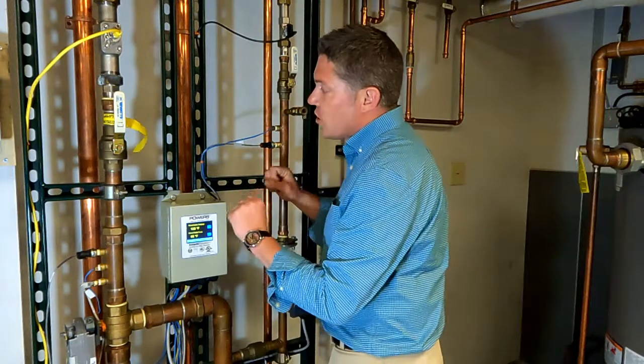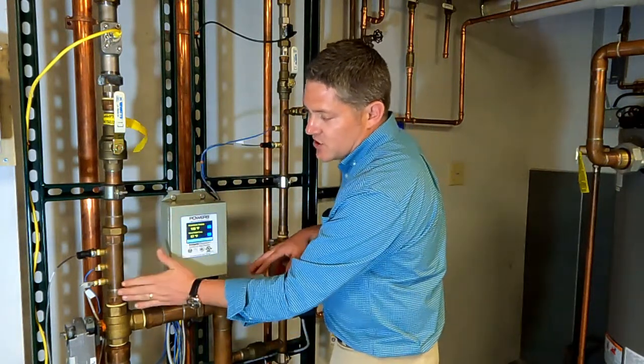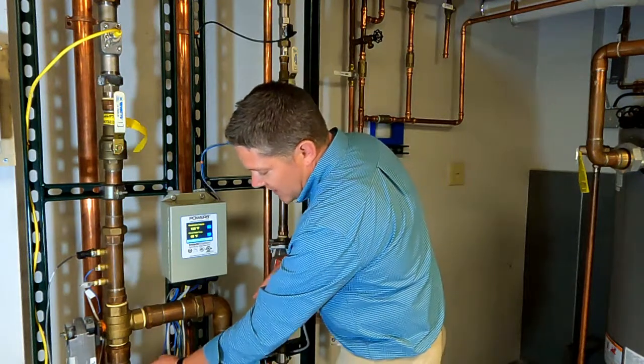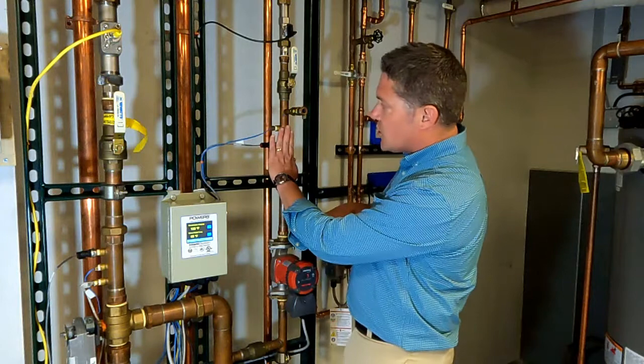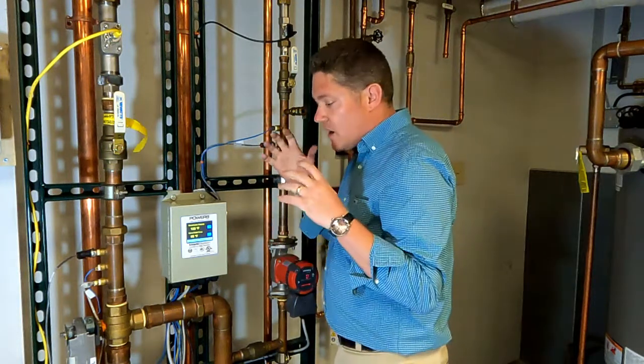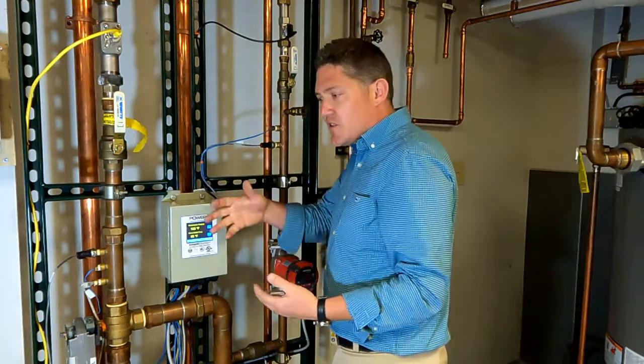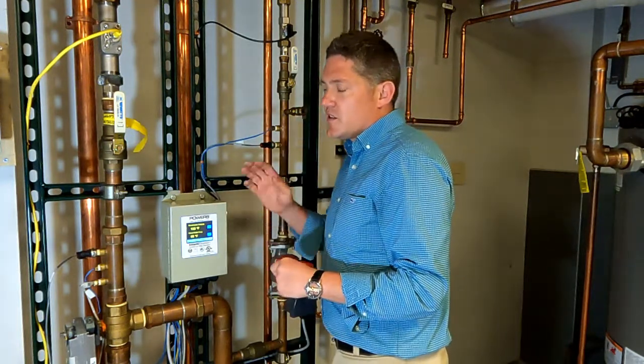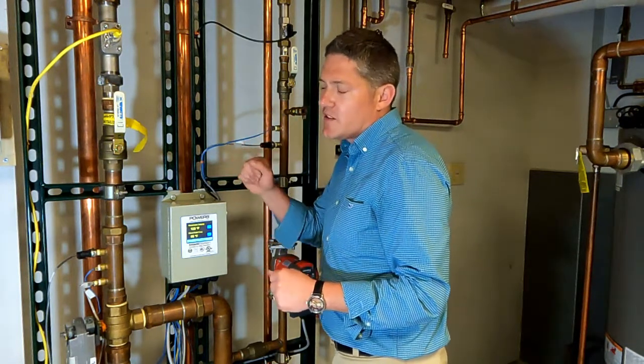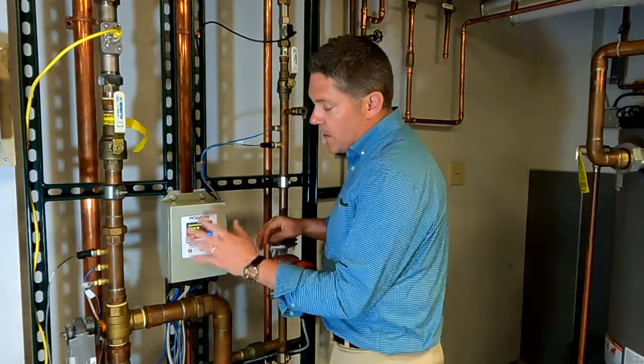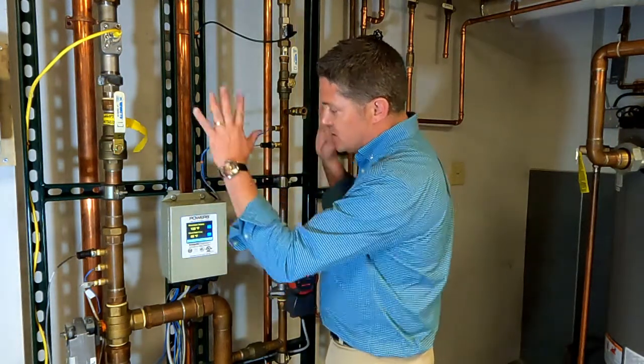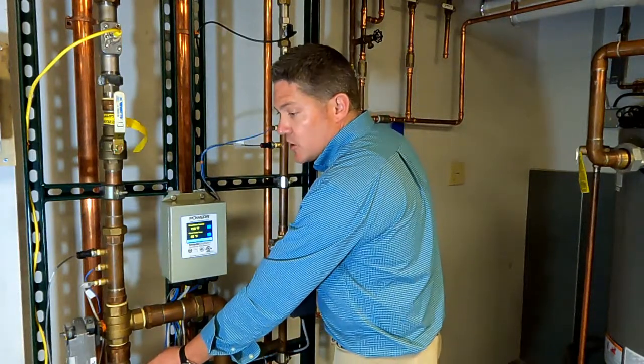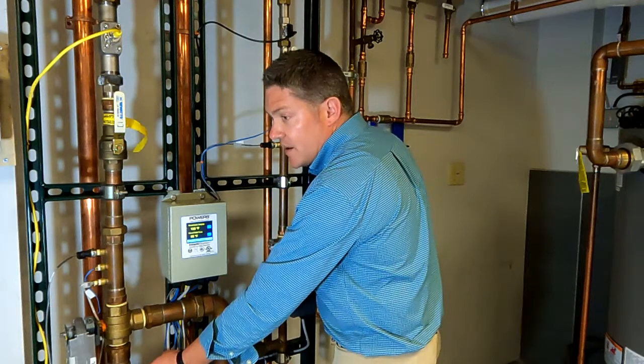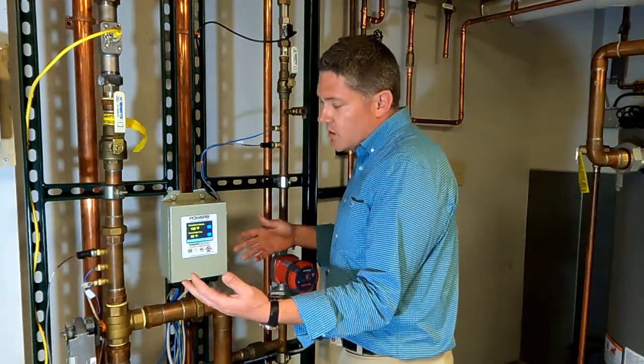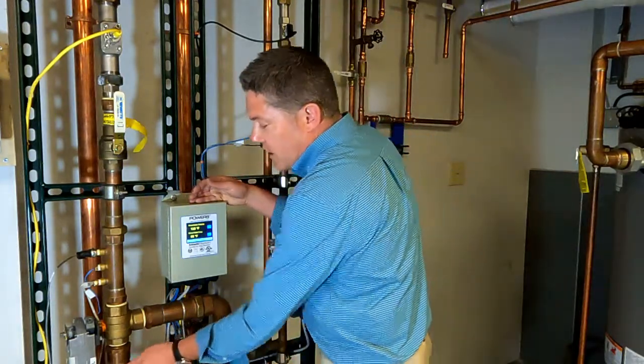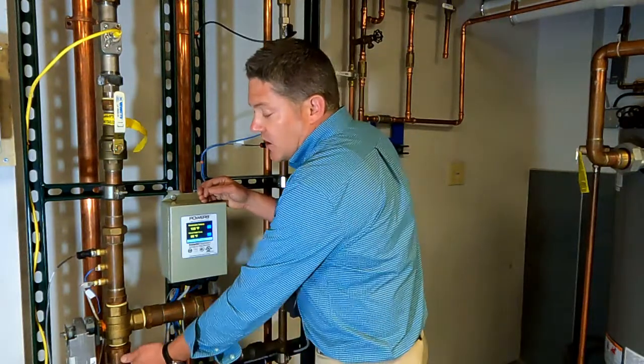mixing valve fails. So on the Intellistation Sr, we have temperature and pressure sensors on your mixed outlet, your hot inlet, your cold inlet, and on your return piping right here. So there's a ton of data here which really helps to troubleshoot problems. So let's say you've got a facility calling and saying, hey, the mixing valve isn't working, we're running out of hot water, or it's not producing hot enough water in the morning. Well, you might be able to come and take a look at your data on this and see all your sensors, and you can say, oh, hey, I see that the hot side inlet had dropped down to 85 degrees. Well, I can't provide 120 to the building if you're only supplying hot at 85 degrees. So that's telling you that you ran out of hot water.